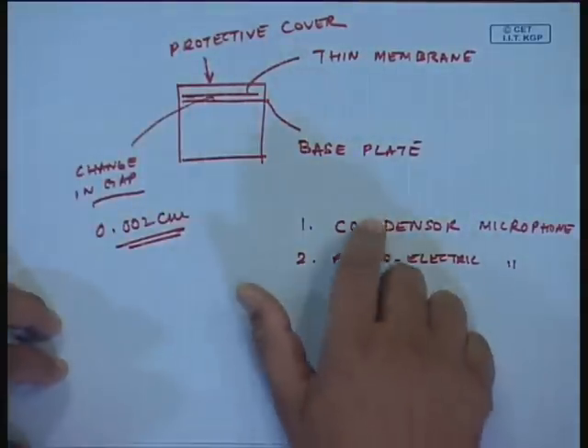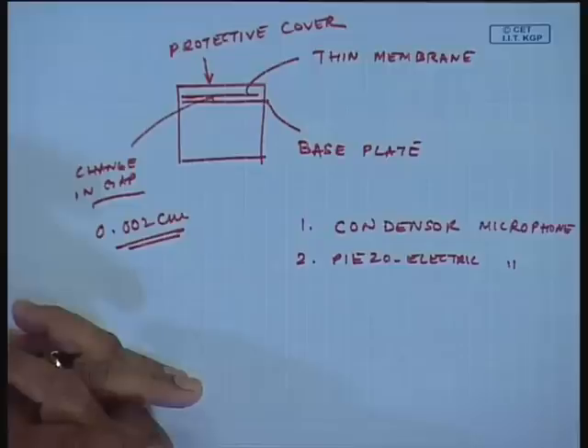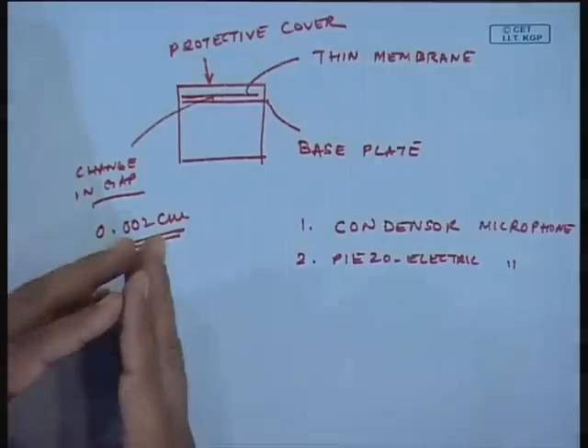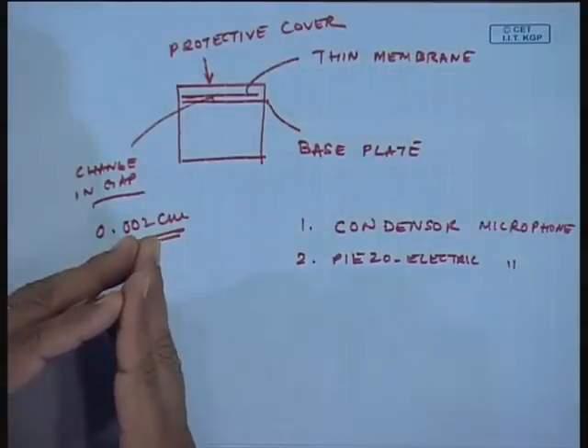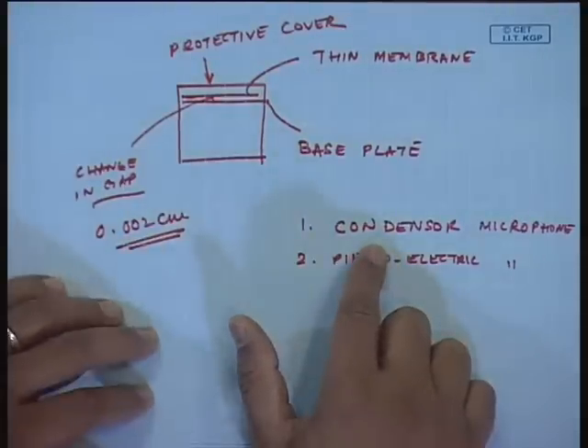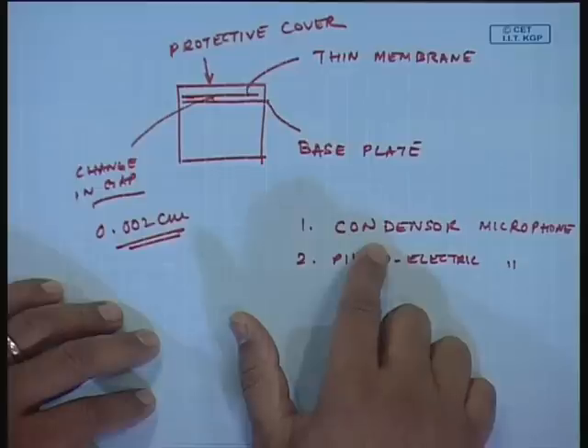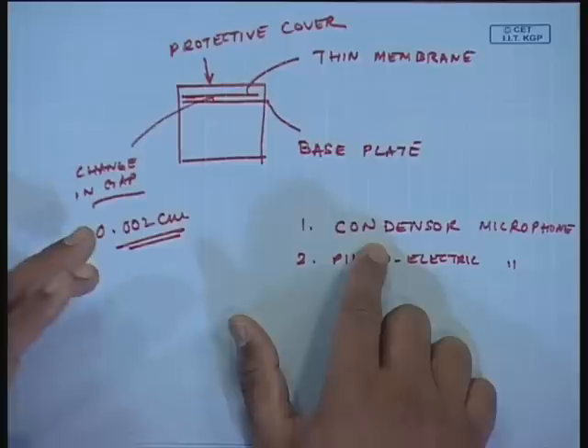Condenser microphones have very, very high dynamic range and a very wide frequency response. They can measure as low as 0.1 hertz to as high as 100 kilohertz. We only hear up to about 20 kilohertz, but there are many ultrasonic phenomena beyond 20 kilohertz which can be monitored through such condenser microphones.